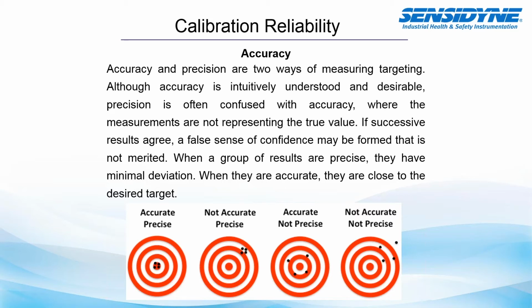So in the illustration below, the illustration to the far left is both accurate and precise. You can see that there's a very tight shot group in the dead center of the target. This is what we want. However, you can be precise but not accurate, which is the second bullseye, which shows a tight group but away from that targeted, or in this case, the desired flow rate. The third one that you see from the left is accurate but not precise. If you averaged out those 4 dots, you would get an average that was very accurate, dead center of that bullseye. But in this case, it's not very precise. And I'll explain how this can be illustrated with some of the sampling. And then, of course, the last illustration there is showing neither accuracy nor precision, as the shot group is spread out, away from your targeted bullseye, the intended calibration flow rate.